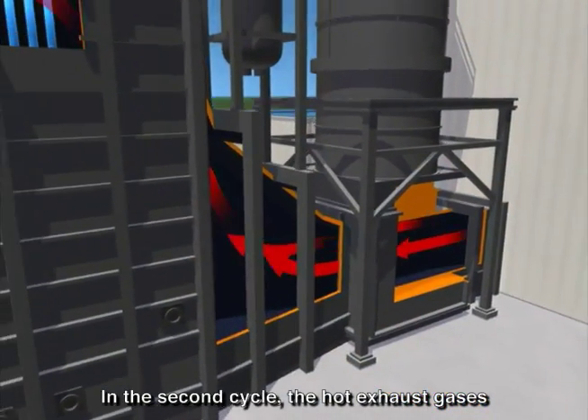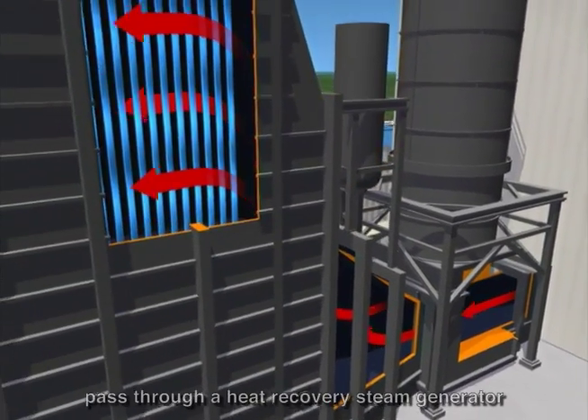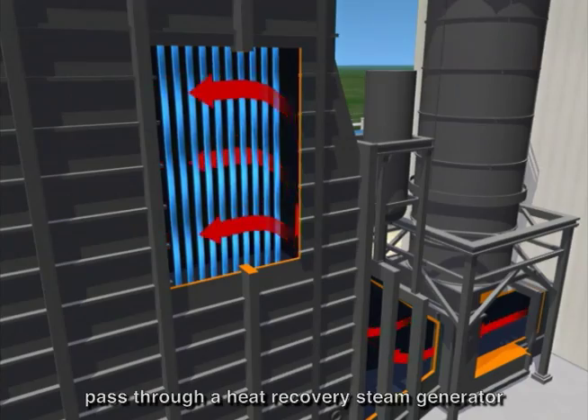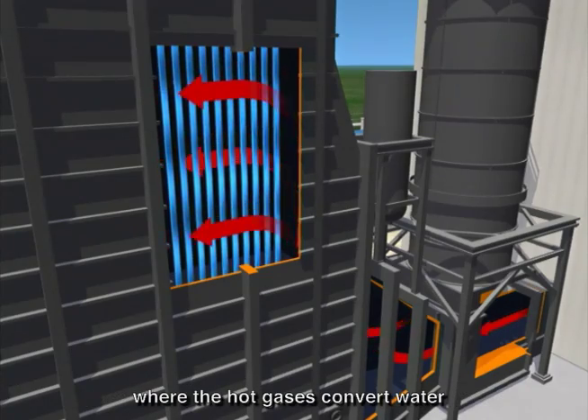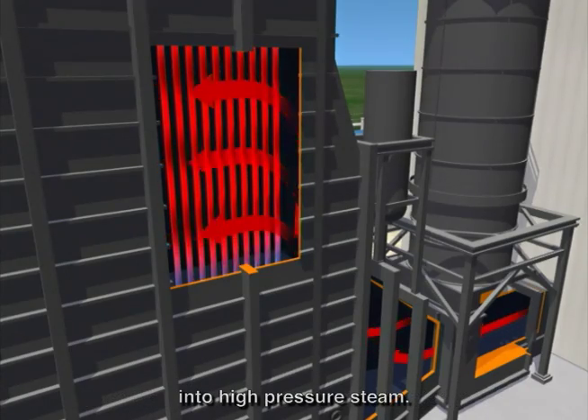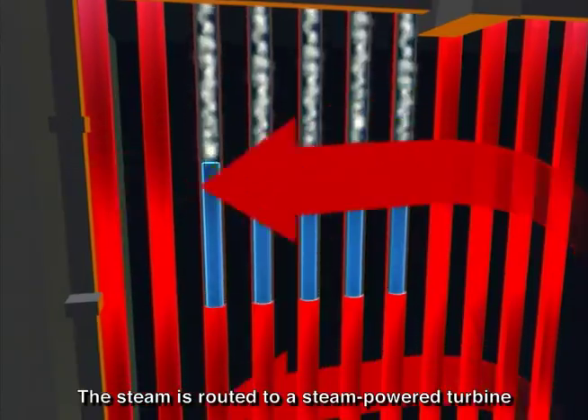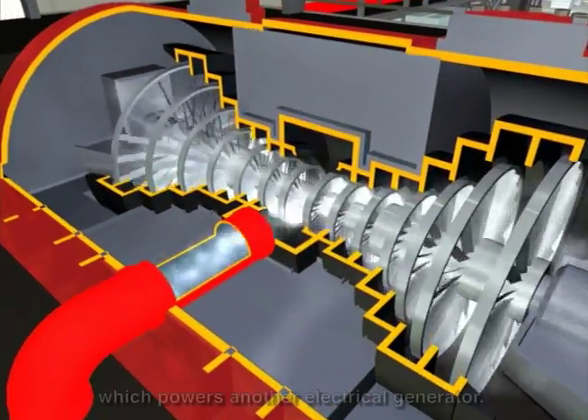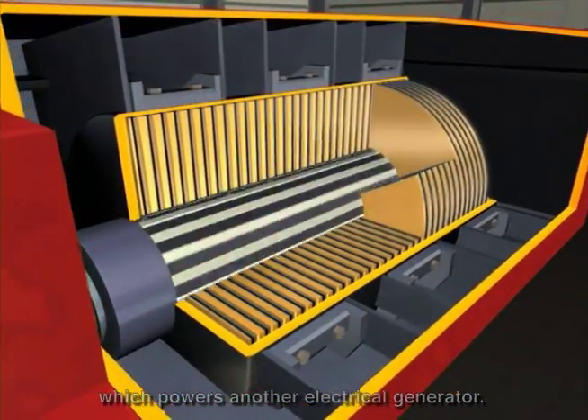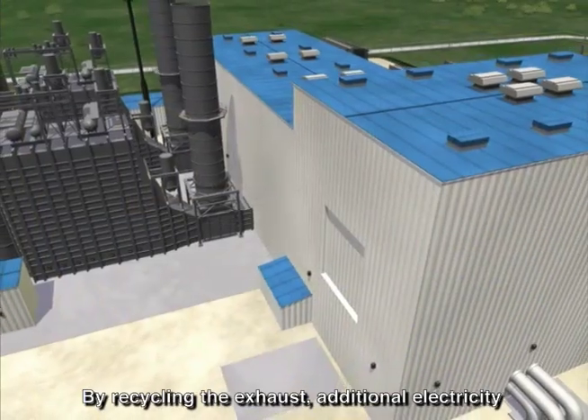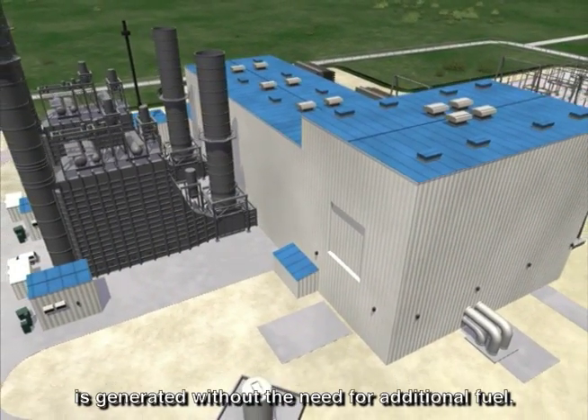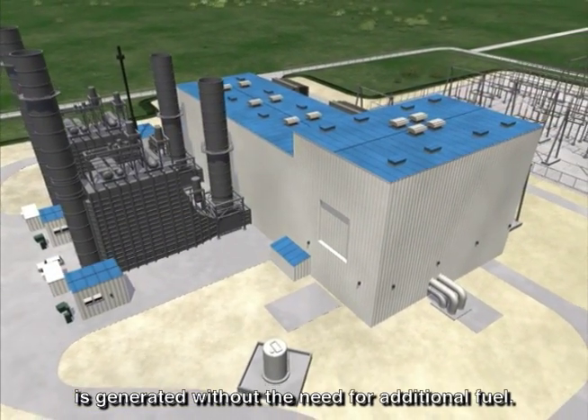In the second cycle, the hot exhaust gases pass through a heat recovery steam generator, where the hot gases convert water into high-pressure steam. The steam is routed to a steam-powered turbine, which powers another electrical generator. By recycling the exhaust, additional electricity is generated without the need for additional fuel.